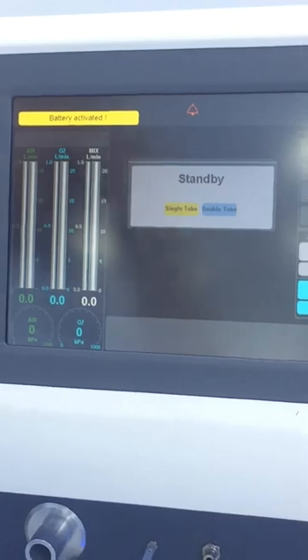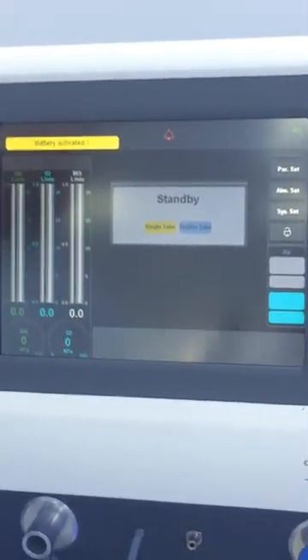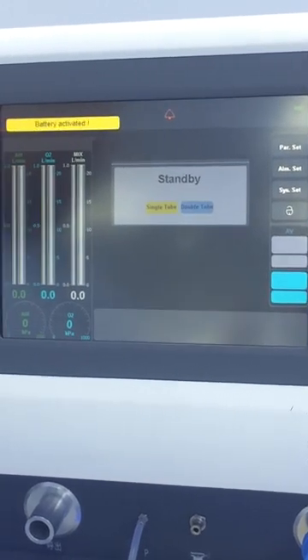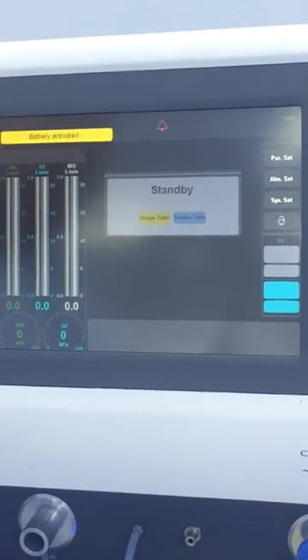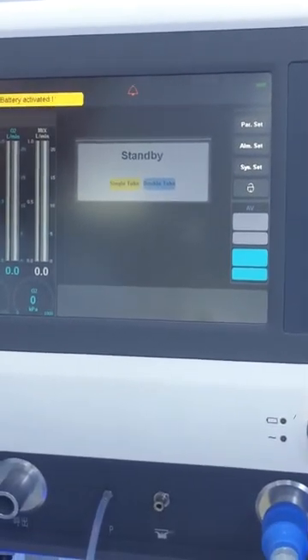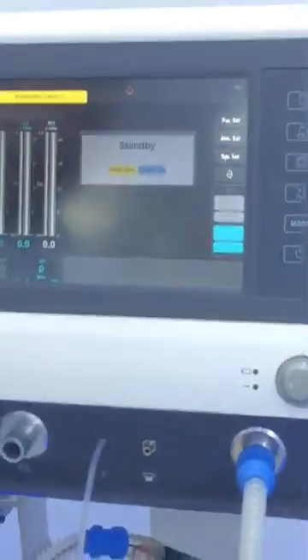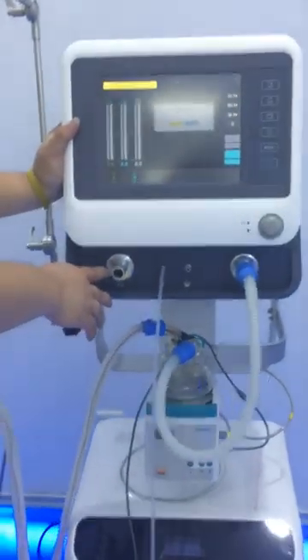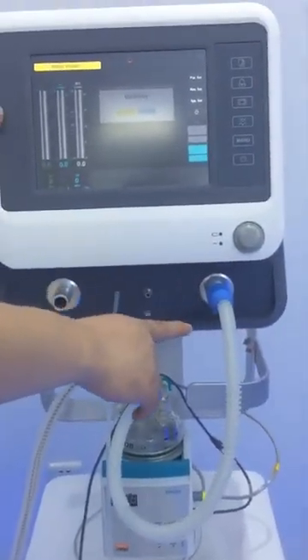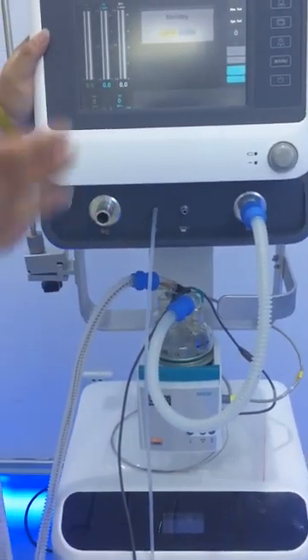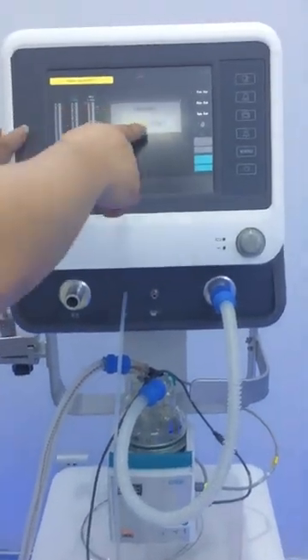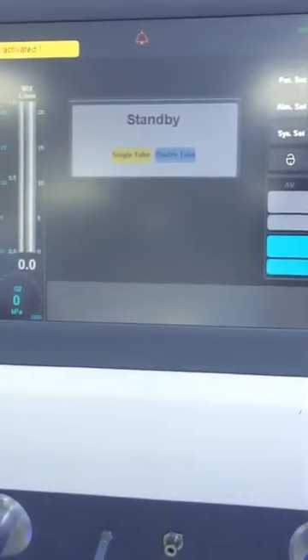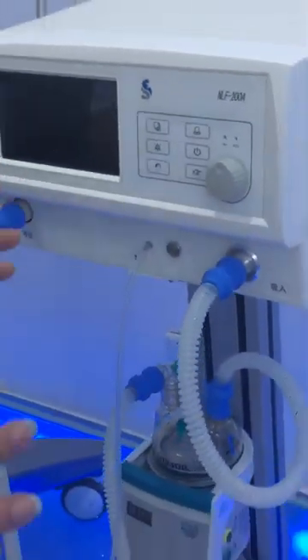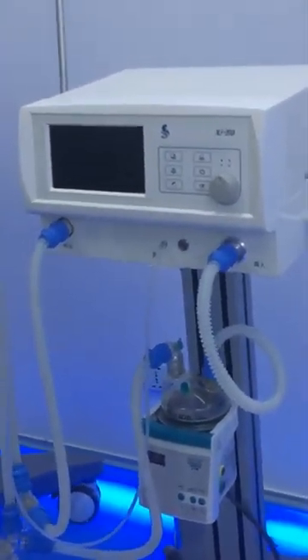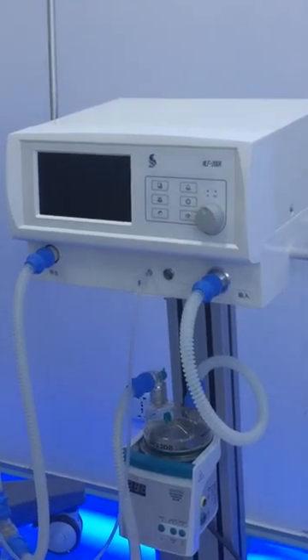Because this is the high-end model of our CPAP system, we have the single tube and double tube. The single tube is used when we are using the BiPAP function, and the double tube is used when we are using the CPAP function. So this machine has the BiPAP ventilation mode. For the single tube, we connect like this. There's no need to connect the exhalation port. We only make a pipeline to connect the inspiration port and then the humidifier, and it can be used, and you can get the BiPAP function. If you want to use the double tube, which means we want to use the CPAP system, then it will be connected like this. That means the inspiration port and the expiration port are both connected, and then the humidifier. So either way you can choose. This is the standard configuration for our high-end CPAP system.